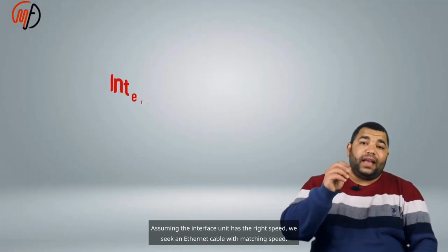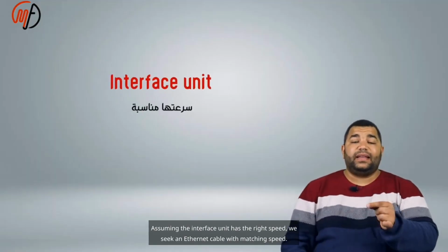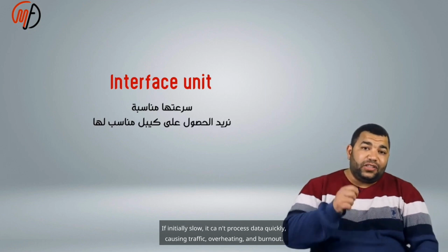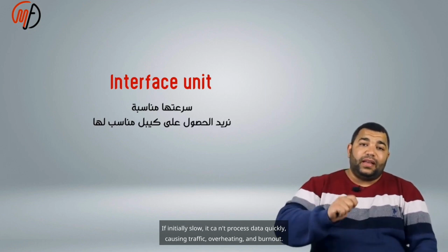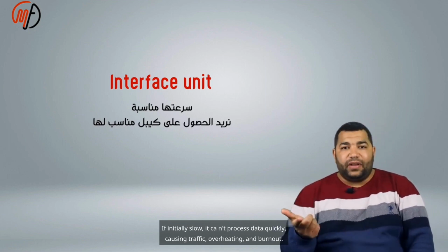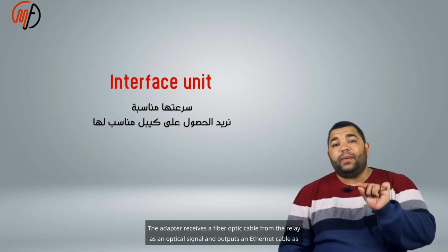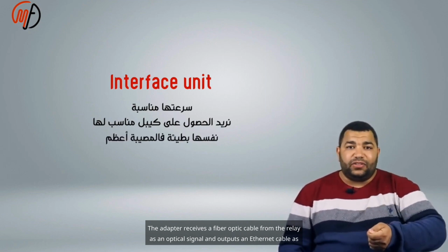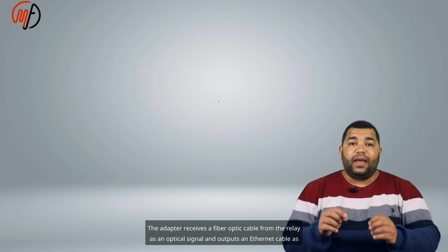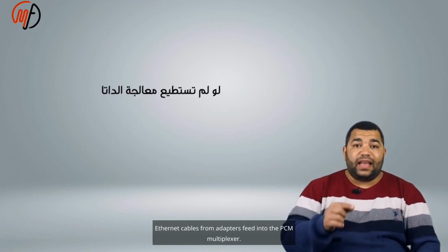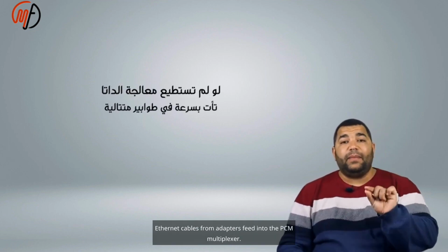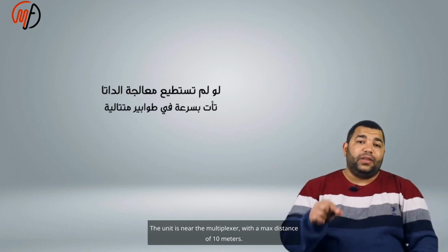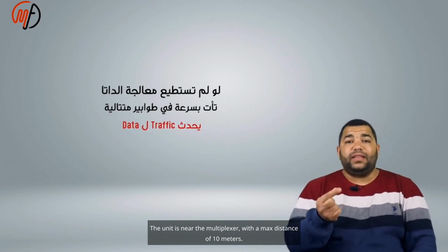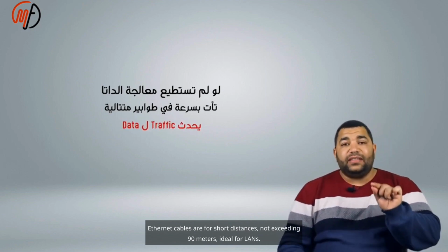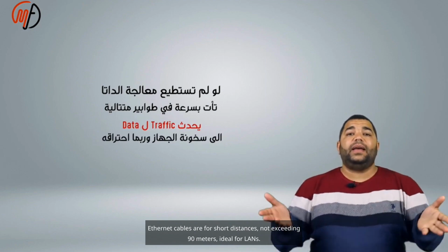Assuming the interface unit has the right speed, we seek an Ethernet cable with matching speed. If it is initially slow, it can't process data quickly, causing traffic, overheating, and burnout. The adapter receives a fiber optic cable from the relay as an optical signal and outputs an Ethernet cable as an electrical signal. Ethernet cables from adapters feed into the PCM multiplexer. The unit is near the multiplexer, with a max distance of 10 meters. Ethernet cables are for short distances, not exceeding 90 meters, ideal for LANs.